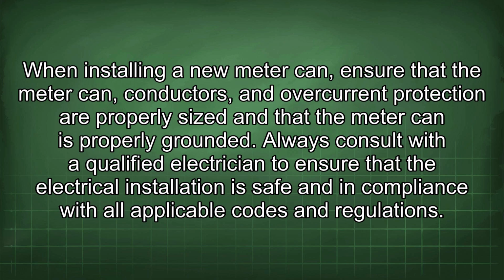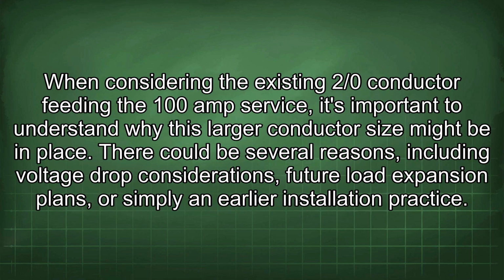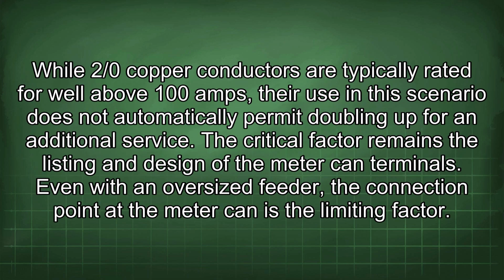When considering the existing 2/0 conductor feeding the 100 amp service, it's important to understand why this larger conductor size might be in place. There could be several reasons, including voltage drop considerations, future load expansion plans, or simply an earlier installation practice. While 2/0 copper conductors are typically rated for well above 100 amps, their use in this scenario does not automatically permit doubling up for an additional service. The critical factor remains the listing and design of the meter can terminals. Even with an oversized feeder, the connection point at the meter can is the limiting factor.